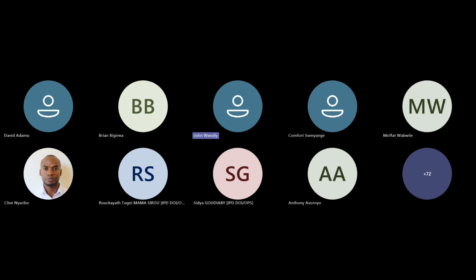Usually those biological indicators are in strip form, Tyvek biological indicators, to allow the vaporized hydrogen peroxide and peracetic acid to penetrate the barrier of the biological indicator and reach the spore organisms. They are mainly located inside the most challenging, worst-case locations within the room, for example in areas far from the tank itself, in dead zones, or in hidden areas within the room.